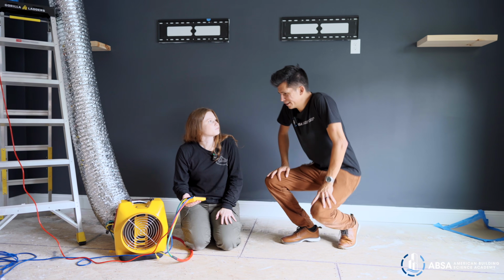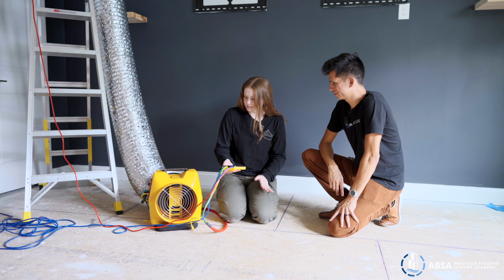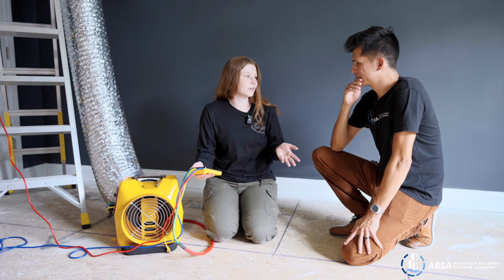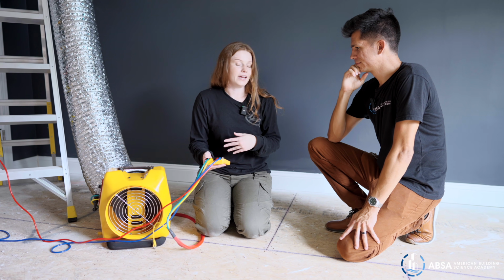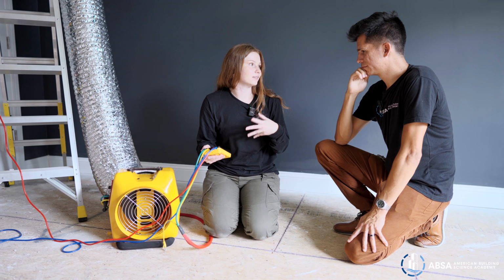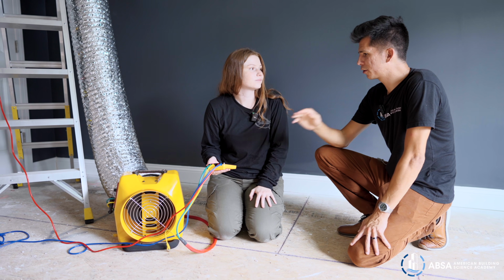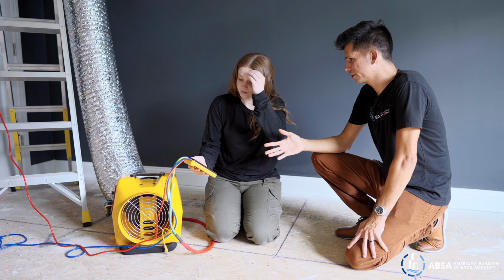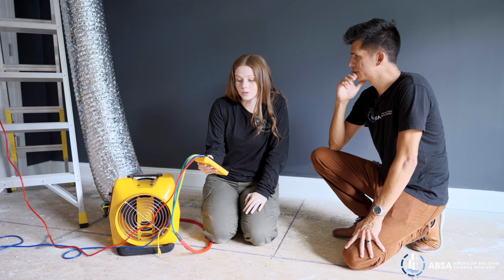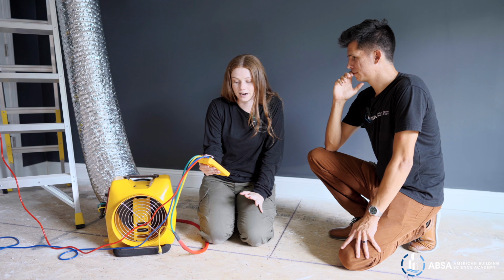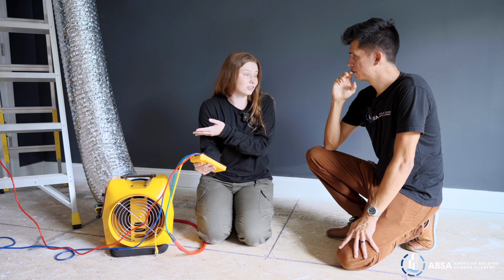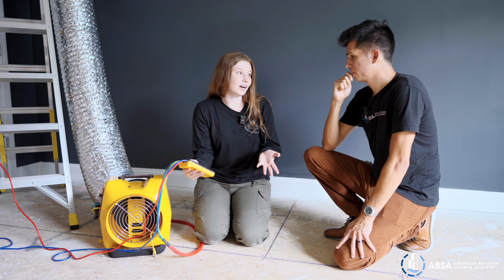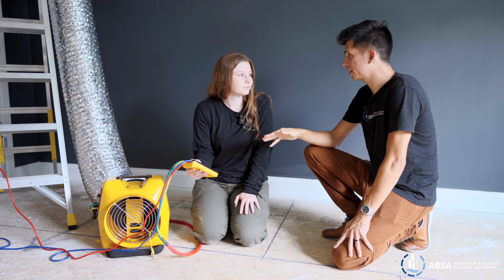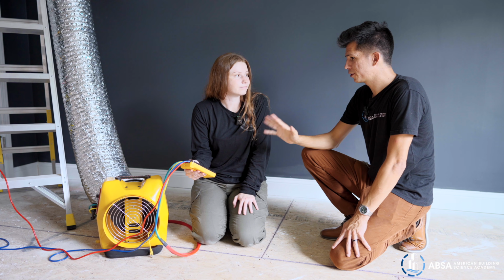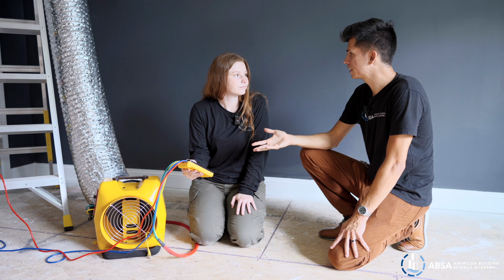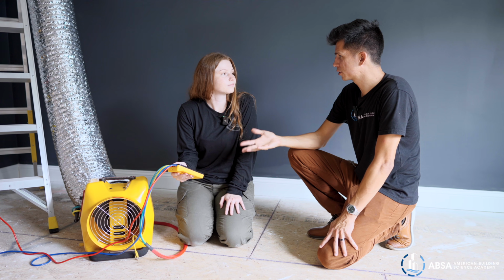Hey Reagan. All right, so what do you got here? What is this thing? This is the duct blaster. What it's doing is pressurizing the ducts, and we're able to measure how much air is leaking into the attic. Okay, and so this manometer is able to tell you how much air leakage there is. What are you seeing here? How much? Right, so we're seeing about 100 CFM of air, which is a lot because this air handler is only moving 600 CFM of air. Okay, so 100 CFM of air is actually leaking into the attic, and the thing's only moving 600. That's like 15% of the air that you're cooling just going right into the attic.